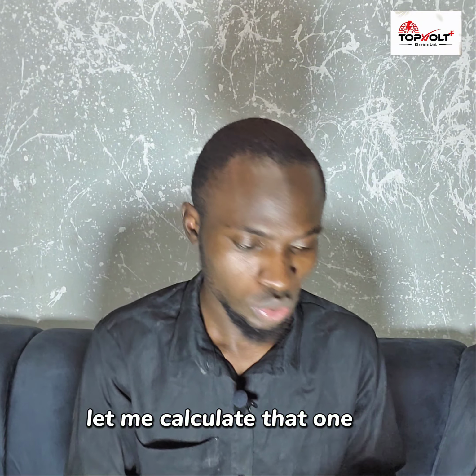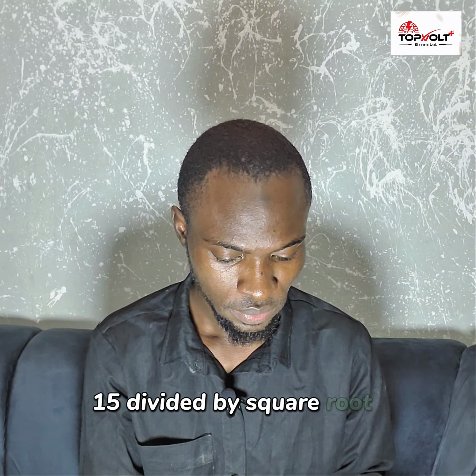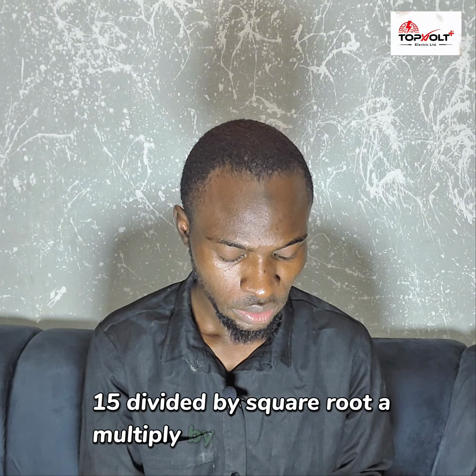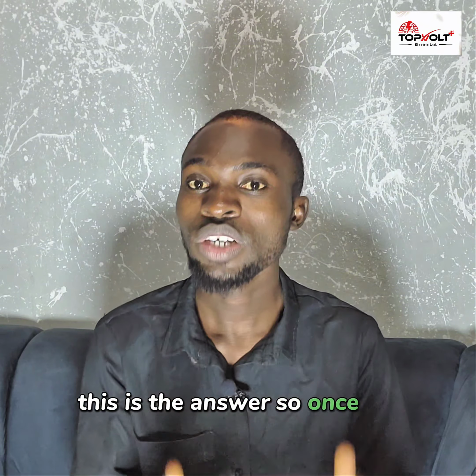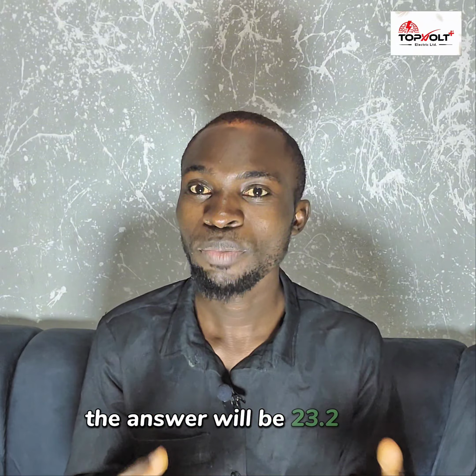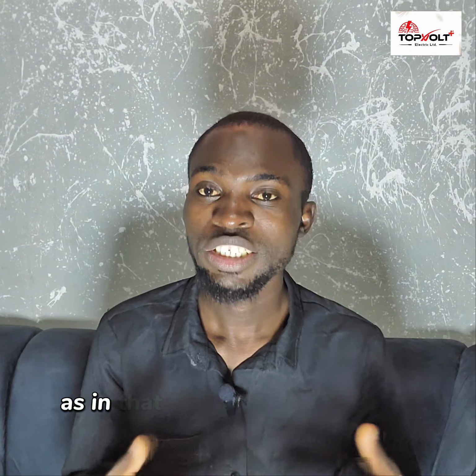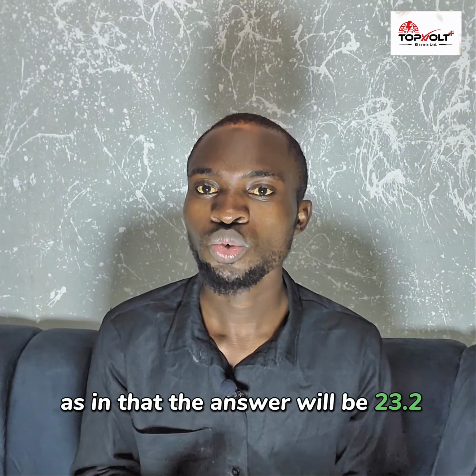Let me calculate that one also. 15 divided by square root of 3 multiplied by 415 multiplied by 0.9. Now this is the answer. So once you calculate it, the answer will be 23.2 amps.